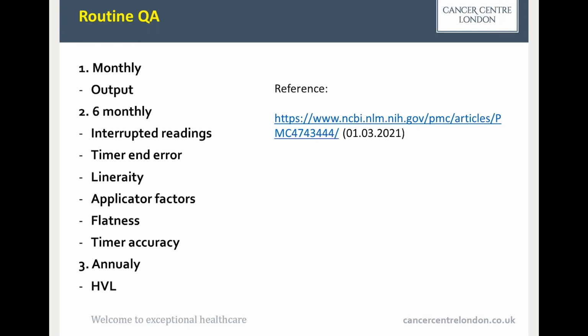We still check flatness, but we don't use a profiler. We don't check profiles. We check with a chamber at specific positions, and because we have collected these baselines for chamber readings, it is enough that we take the biggest applicator and measure at sensible points from the central axis, and confirm that the measured off-axis values are stable and agree with our baselines.